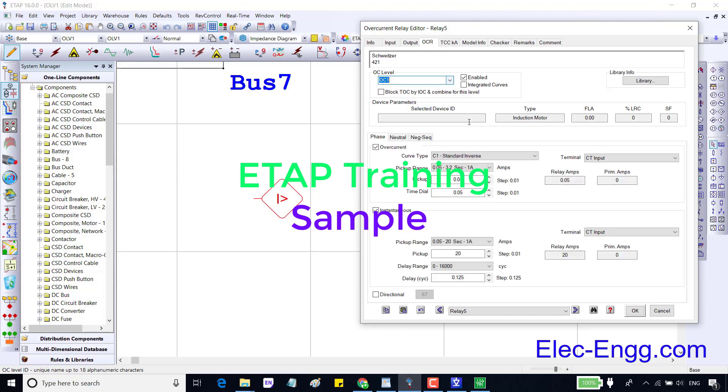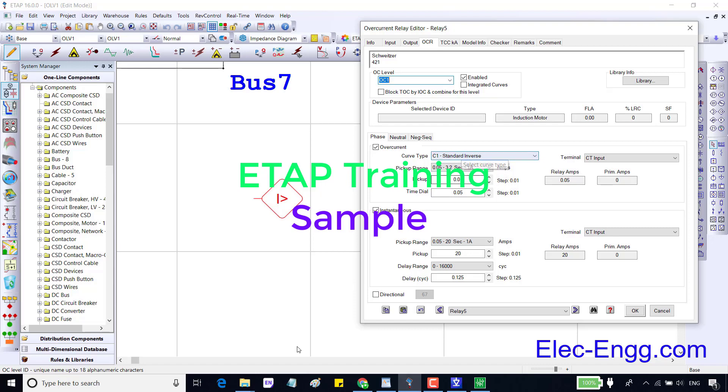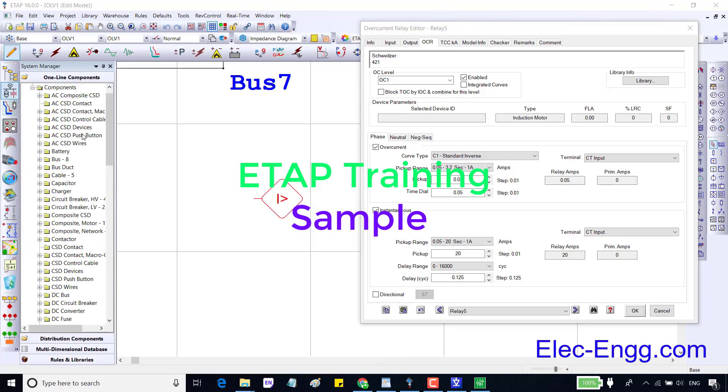Different manufacturers use different names or symbols for these functions. IDMT or inverse time or ANSI 51 all the same function. DMT definite time or instantaneous or ANSI 50 are also the same. Let's open the configuration software AcSELerator QuickSet and add a relay SEL-421 to check the over current function and stages.